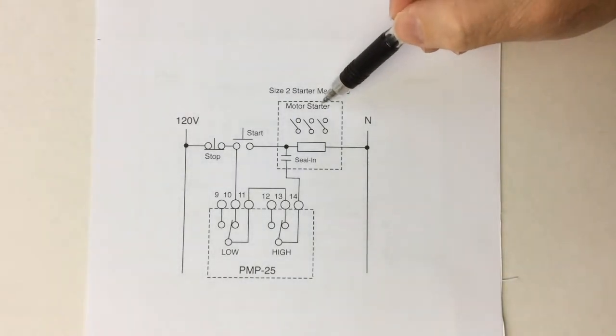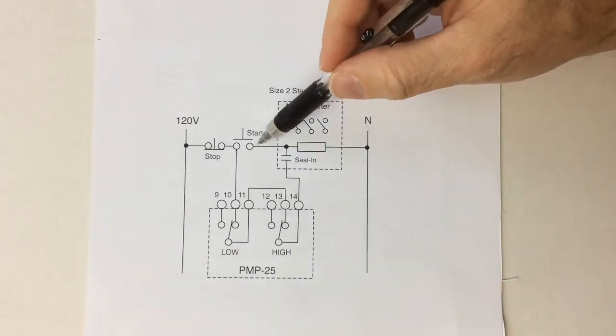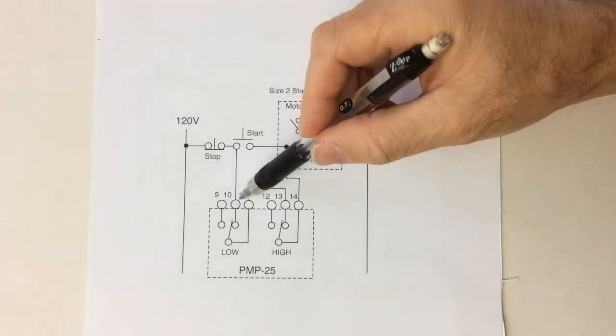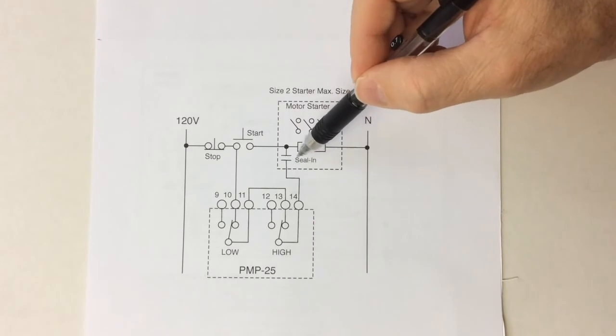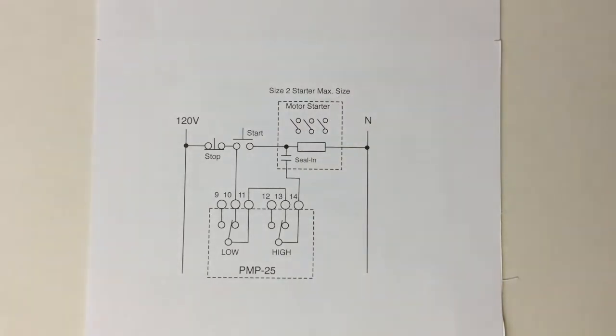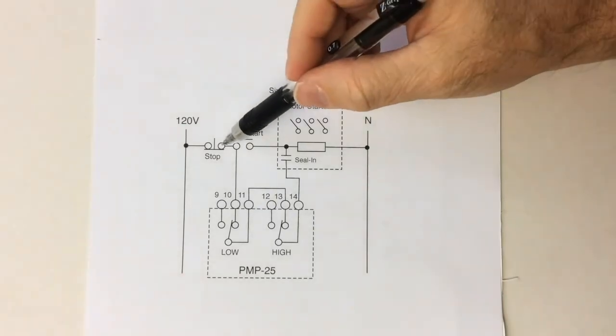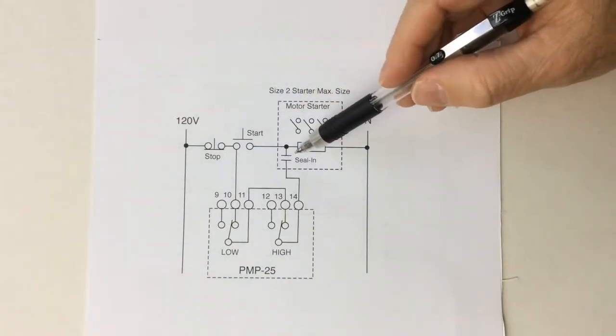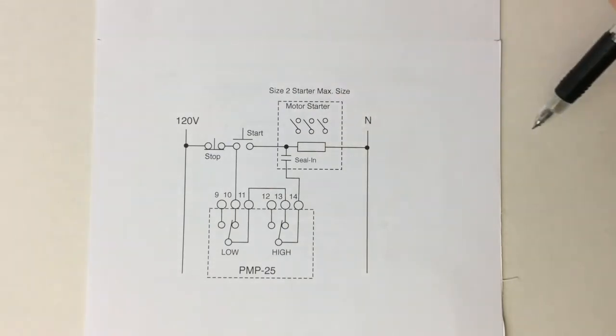After the start button is closed and the motor starts, the starting coil is held on by the stop button, the PMP25 contacts, and the seal-in contact. If the stop button or either of the PMP25 contacts open, the starting coil will de-energize and open the seal-in contact. The motor will shut down and wait for a start.